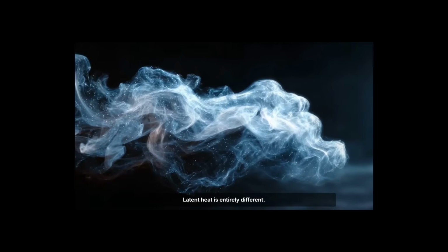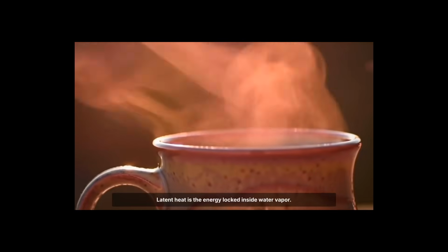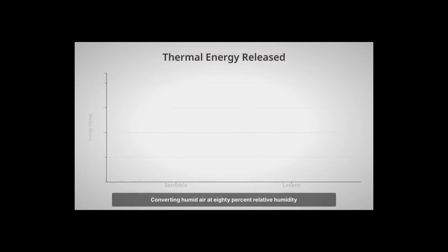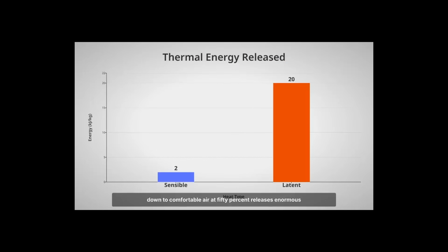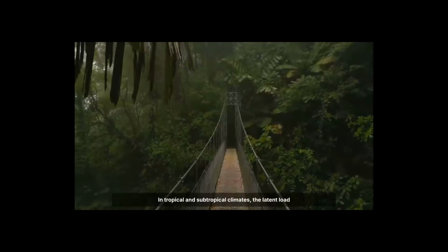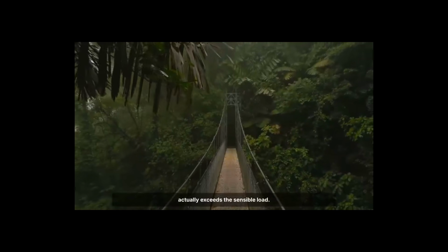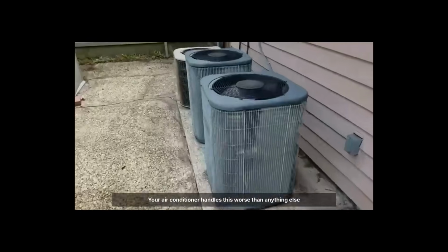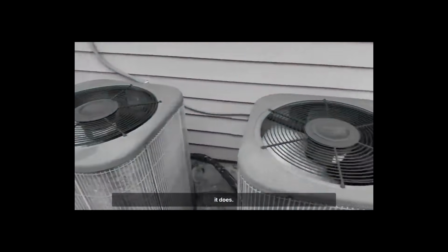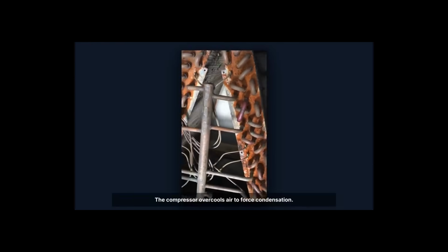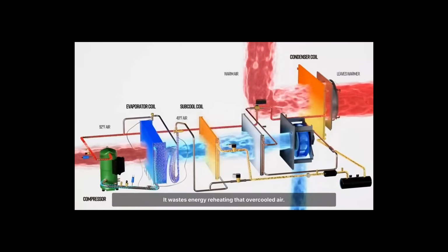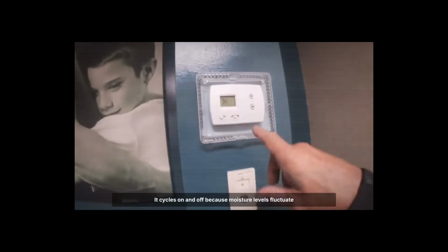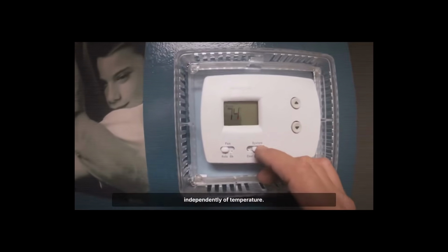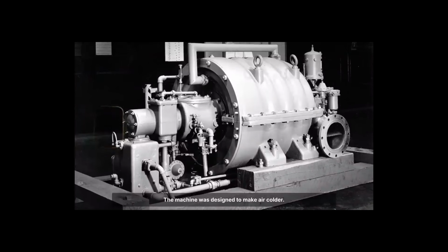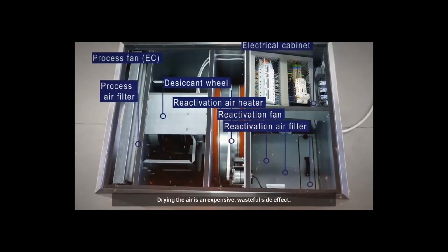Latent heat is entirely different. Latent heat is the energy locked inside water vapor. Converting humid air at 80% relative humidity down to comfortable air at 50% releases enormous thermal energy. In tropical and subtropical climates, the latent load actually exceeds the sensible load. Your air conditioner handles this worse than anything else it does. The compressor overcools air to force condensation. It wastes energy reheating that overcooled air. It cycles on and off because moisture levels fluctuate independently of temperature. The machine was designed to make air colder. Drying the air is an expensive, wasteful side effect.